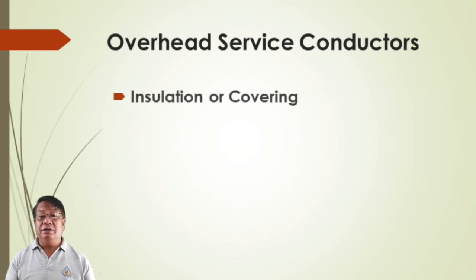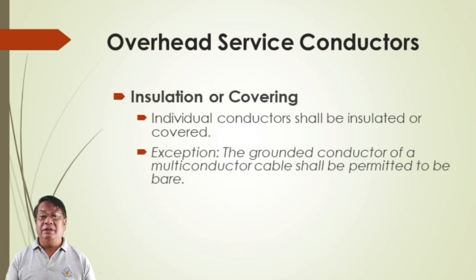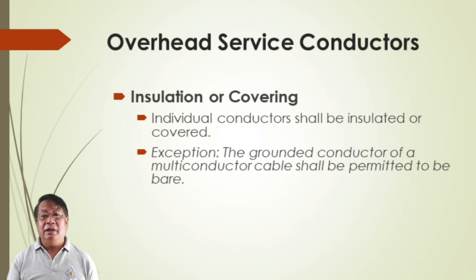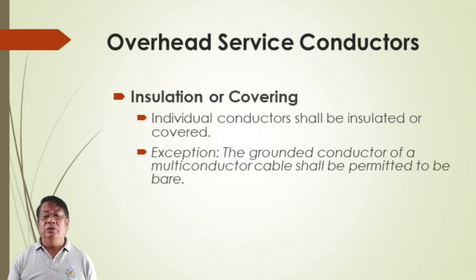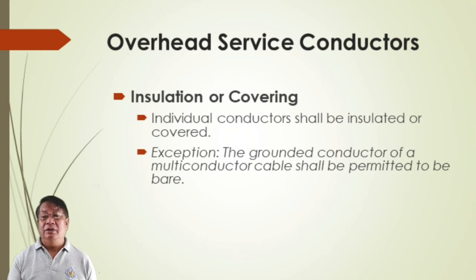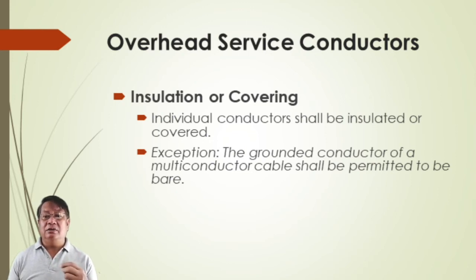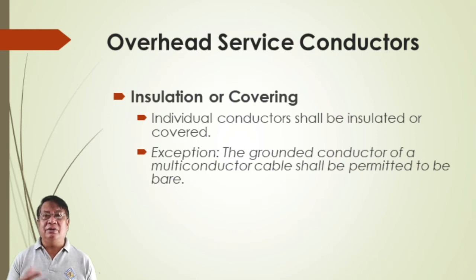The grounded conductor is permitted to be bare or without insulation — or it may have green, white, or gray-striped insulation. For size and rating, the conductor shall have sufficient capacity to carry the load current and adequate mechanical strength. For underground service conductors, the grounded conductor shall be permitted to be uninsulated: bare copper used in a raceway, or bare copper for direct burial where bare copper is judged suitable for soil conditions.